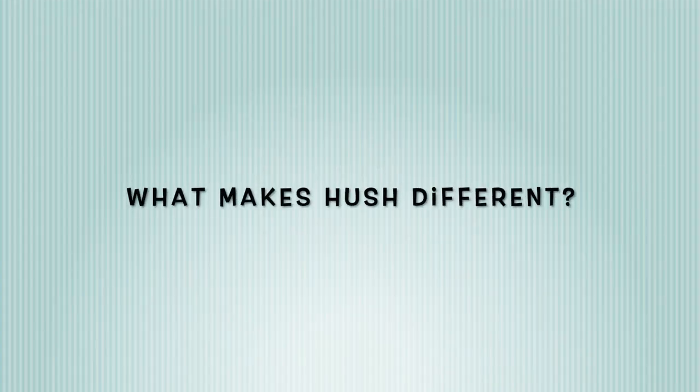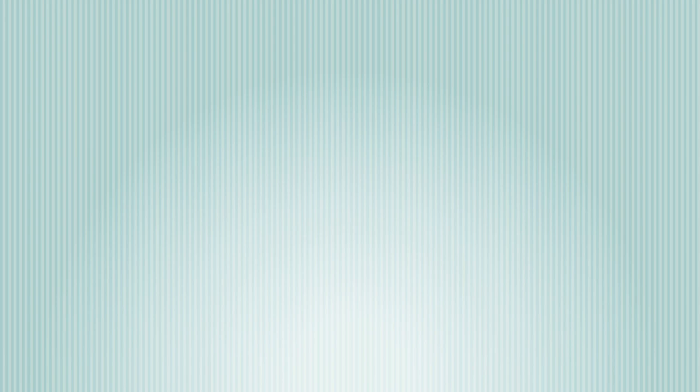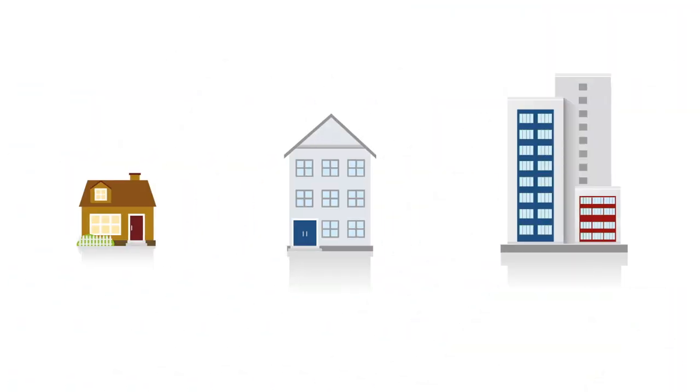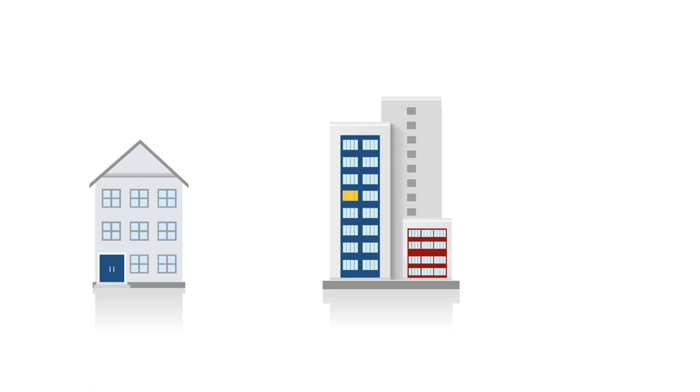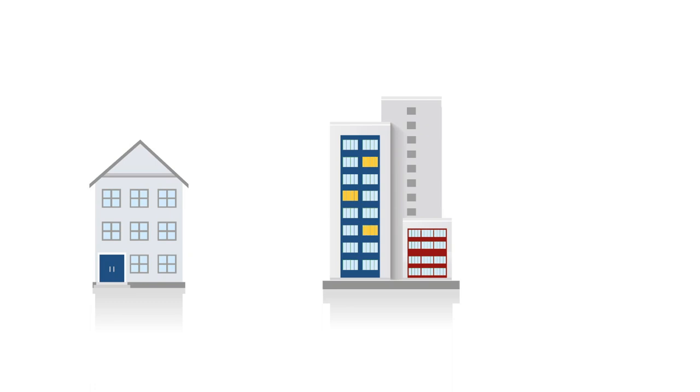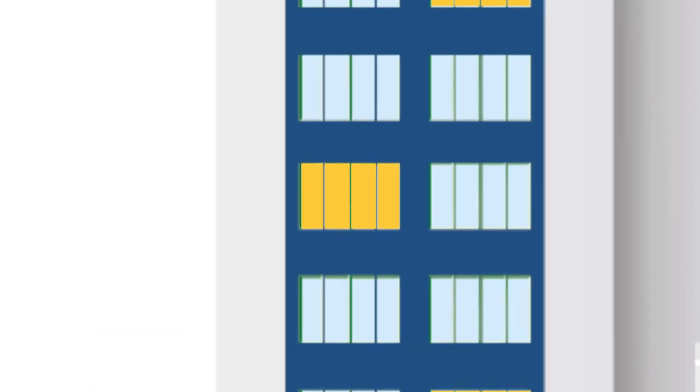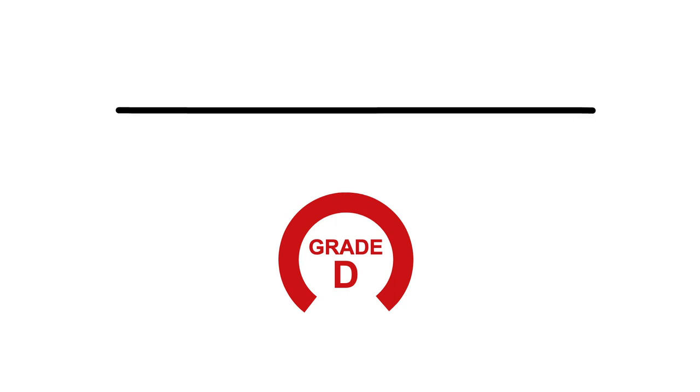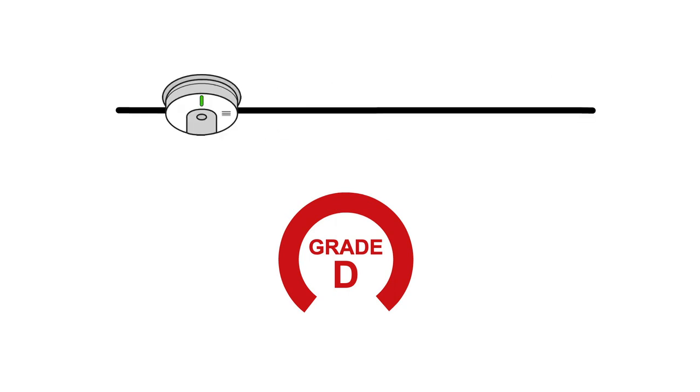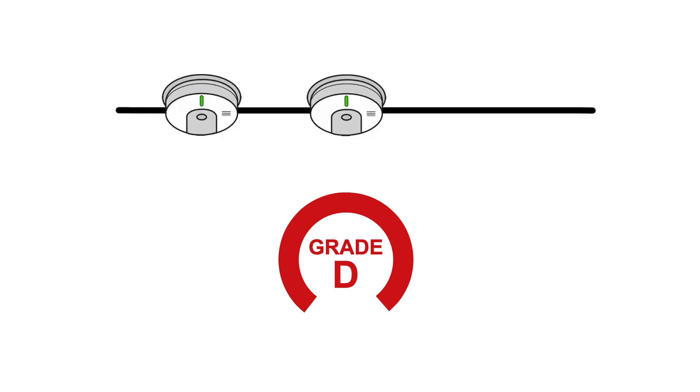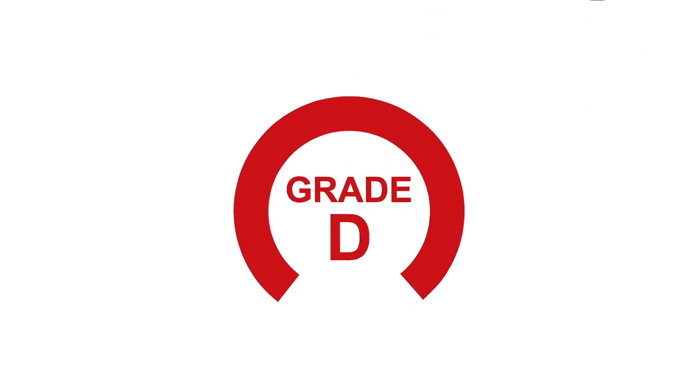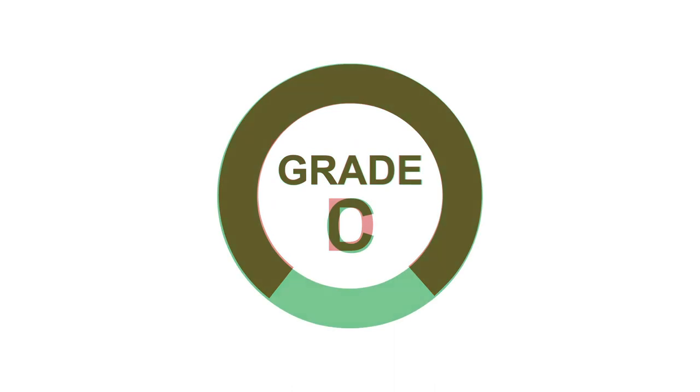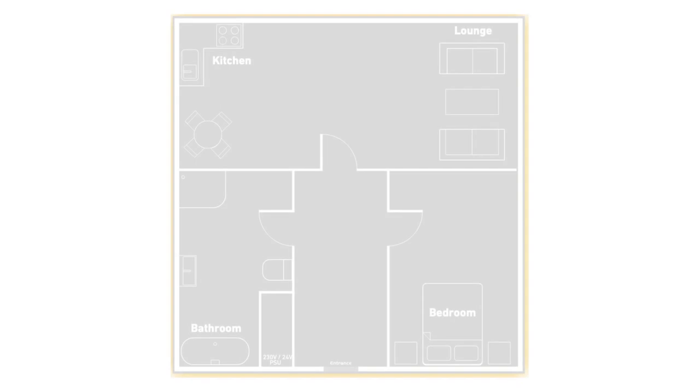What makes Hush different? Most new residential dwellings, including flats and apartments within purpose-built tower blocks, are fitted with Grade D mains battery alarms, the minimum grade recommended by BS5839 Part 6. As Hush is a Grade C system, it offers a higher level of protection than a typical Grade D system.